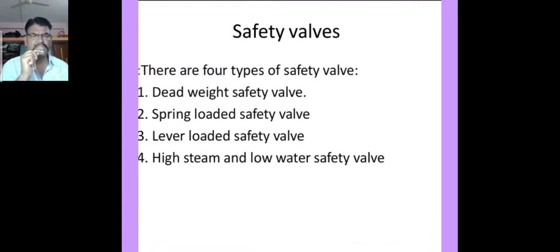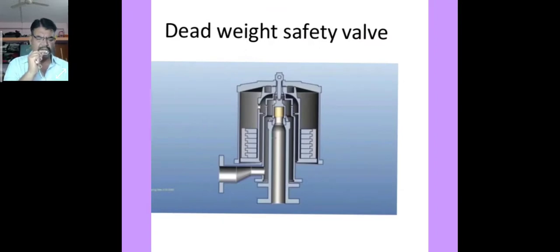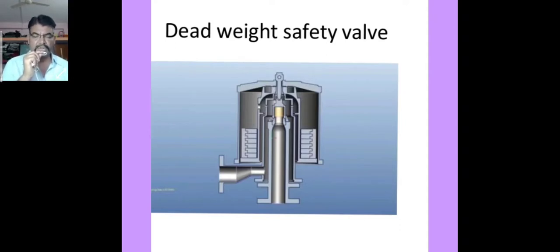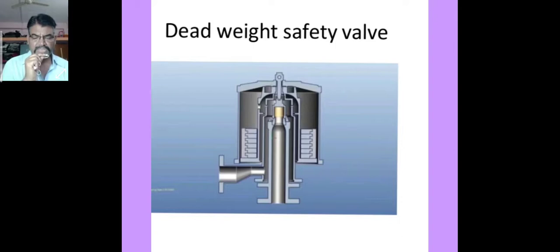There are different types of safety valve: dead weight safety valve, spring loaded safety valve, lever loaded safety valve, and high steam and low water safety valve. The dead weight safety valve is mounted on the boiler shell with a bottom flange. It consists of a gun metal valve mounted on a gun metal seat, with a vertical cast iron pipe through which steam pressure acts. A weight carrier is provided with cylindrical discs of weight and a cover plate. The steam pressure acting upward is balanced by the combined load of the dead weights, weight carrier, and cover plate.